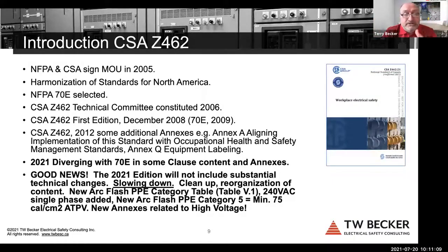And then I'm going to present that in Z462, we made some changes to the arc flash PPE category table method that aren't in 70E. And that is also a significant technical change. And we also added an alternate arc flash PPE category table. Again, there's a whole story there that I don't have enough time to get into, but we have two actual arc flash PPE category tables for AC electrical equipment in Z462, and 70E will only have the original AC equipment table in the arc flash PPE category method.